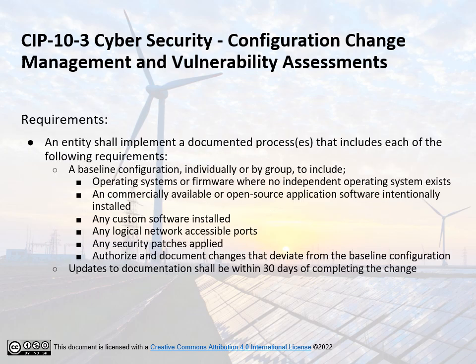CIP-010-3 Configuration Change Management Vulnerability Assessments. Requirements: an entity shall implement a documented process that includes each of the following requirements: a baseline configuration, individually or by group, to include operating systems or firmware where no operating systems exists, a commercially available or open source application software intentionally installed, any custom software installed, any logical network accessible ports, any security patches applied; authorize and document changes that deviate from the baseline configuration. Updates to documentation shall be made within 30 days of completing the change.